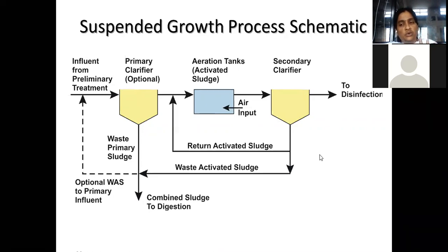The bottom line you can note down: at this stage, when the entire organic impurities are being finished by them, the microorganisms are very active to decompose further material. That's why this active part of the microorganisms we are recycling here. Instead of waiting to get new microorganisms to decompose the impurities, we are recirculating some part of the active material back to the aeration tank.